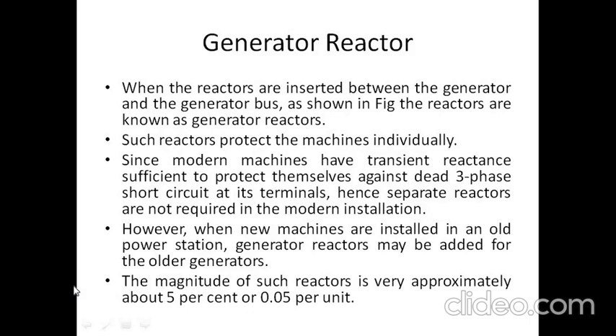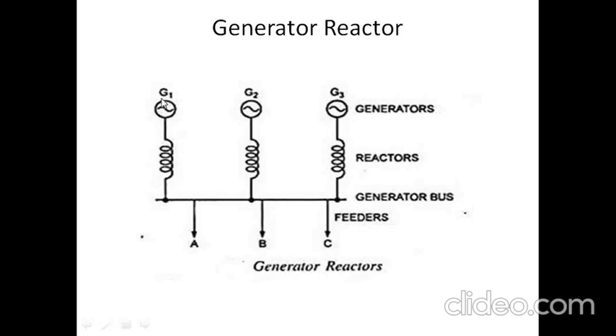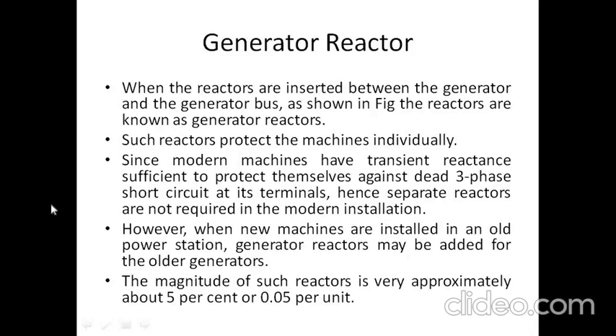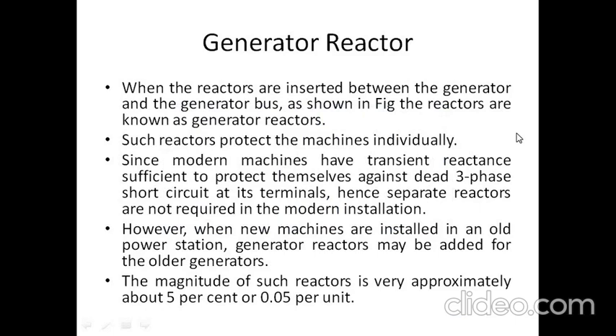Such reactors protect the machines individually, with a separate reactor coil connected along with each individual generator. However, since modern machines have transient reactance sufficient to protect themselves against a dead three-phase short circuit at their terminals, separate reactors are not required in modern installations. In modern installations, the transient reactance is considered sufficient against different faults, so a separate reactor coil is not required in recent installations.